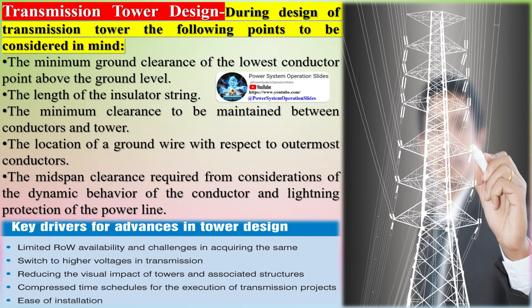During the design of a transmission tower, the following points must be considered: the minimum ground clearance of the lowest conductor above ground level; the length of the insulator string; the minimum clearance to be maintained between conductors and the tower; the location of the ground wire with respect to the outermost conductors; and the mid-span clearance required for dynamic conductor behavior and lightning protection.